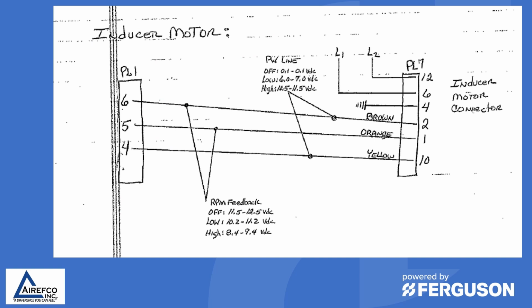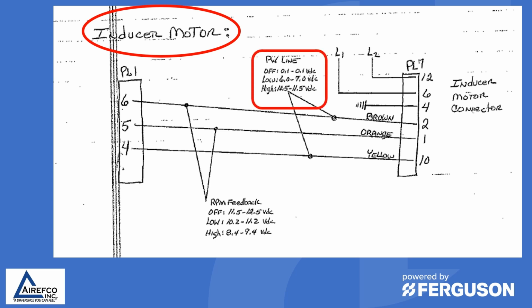So this is a graphic of what our troubleshooting guide is showing us, and here we're checking an inducer motor, and we're checking the pulse width line from the board to the inducer motor. On the off cycle, we should have very little DC voltage of 0.1. When the inducer is commanded in low speed, you should have 6 to 7 volts DC, and at high speed, 10.5 to 11.5 DC between the brown and the yellow wire.